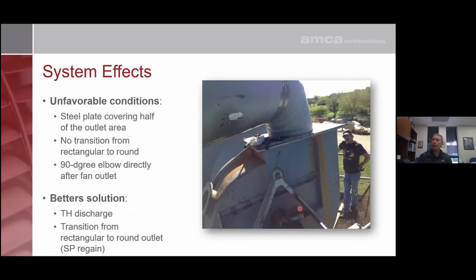Here we have another guy. He's actually pretty proud of his installation. He was willing to pose for this. This is not a very good installation. There's the discharge of the fan, trying to adapt this large rectangular discharge to this round piece of ductwork. Air, again, hugs the outside of the blue shape, deadheads, and has to get forced back in through this piece of ductwork. This fan's, again, not going to perform as cataloged.